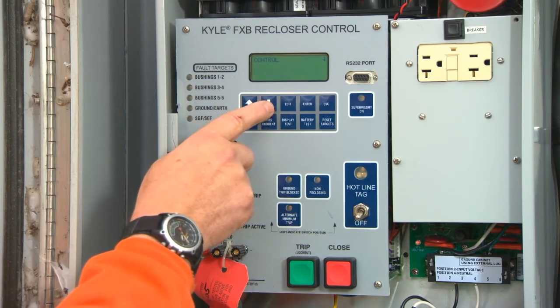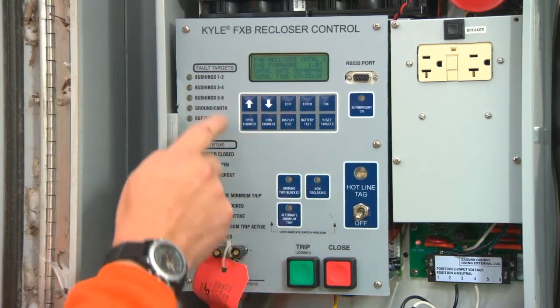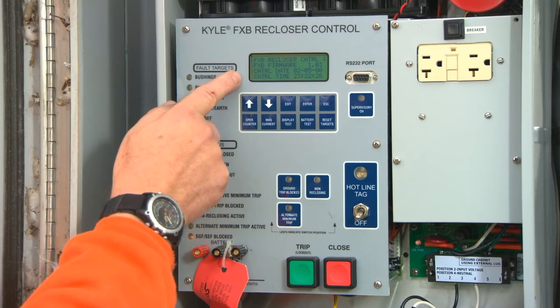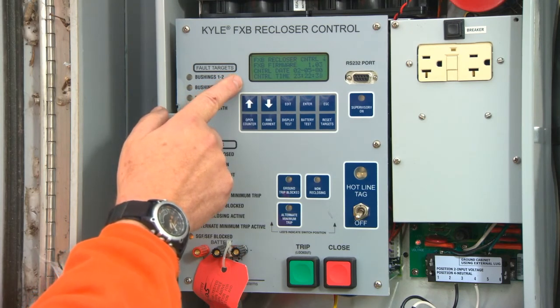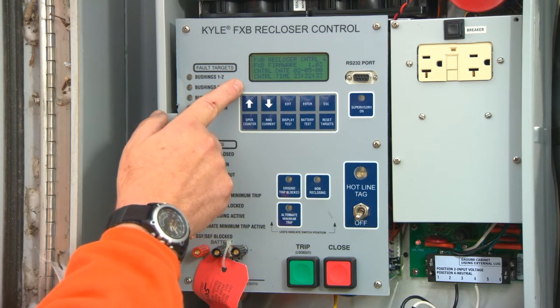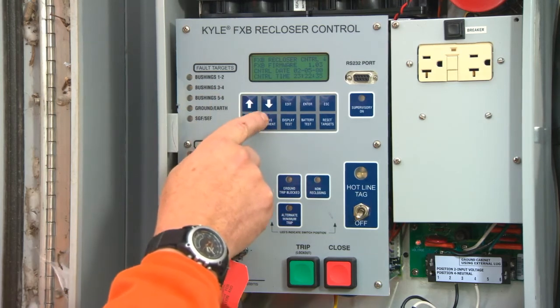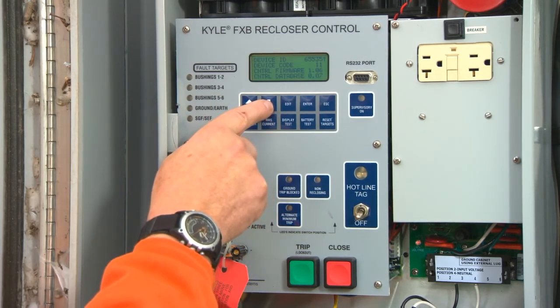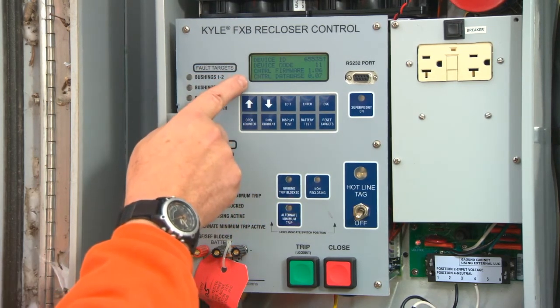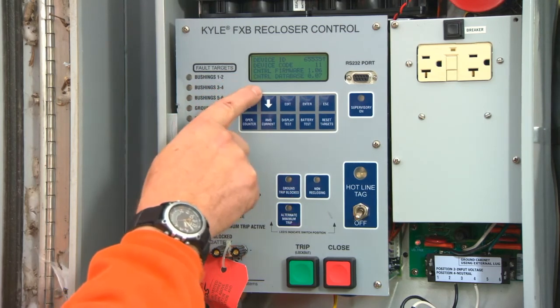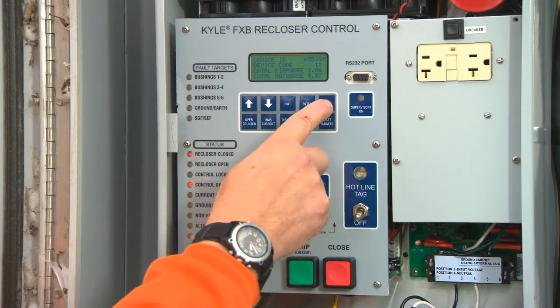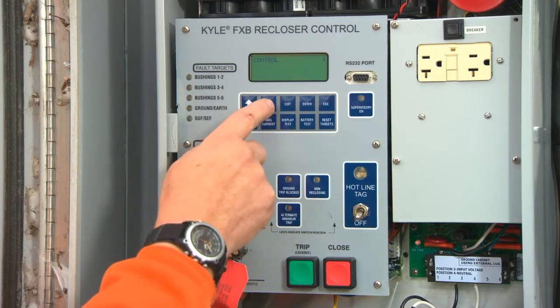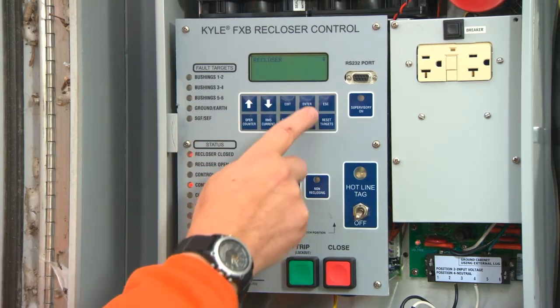The screen will now display the type of control, the firmware version, and the control date and time that are currently programmed. Now, pressing the down arrow will display Device ID, Control Firmware, and Control Database Release versions. Now, press Escape to return to Control. Press the down arrow and then Enter.